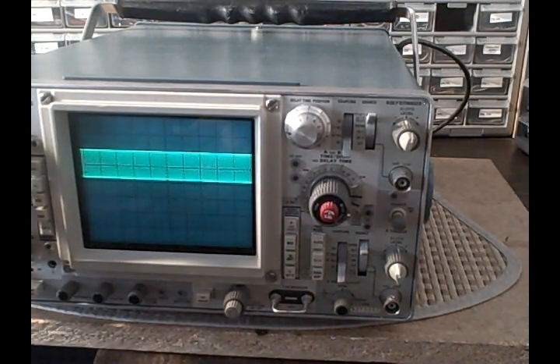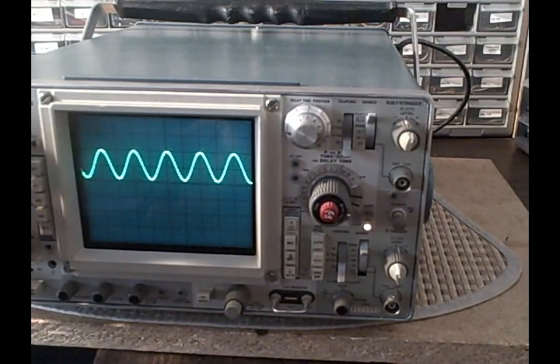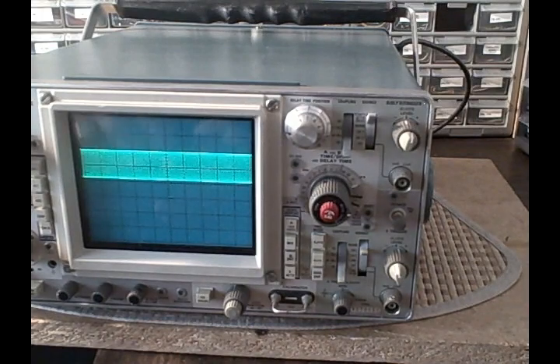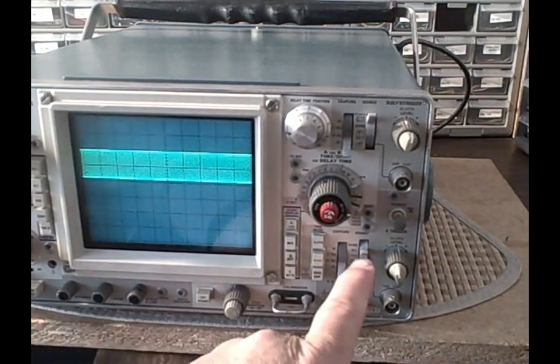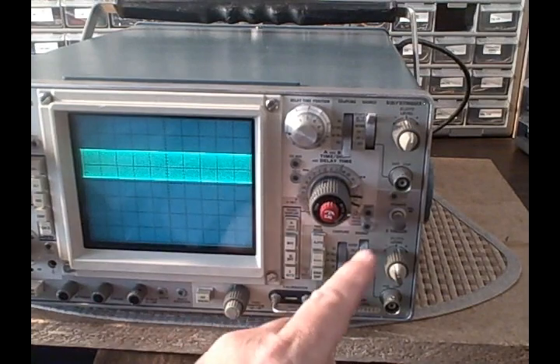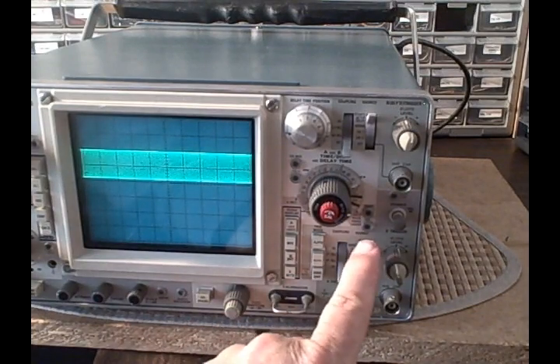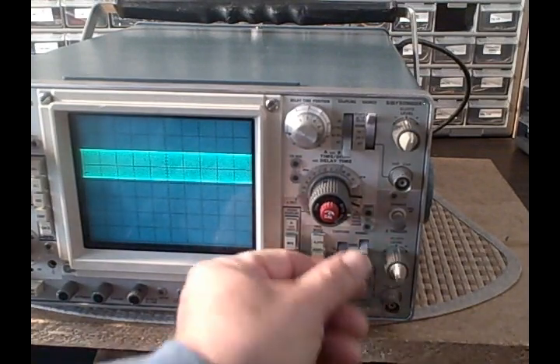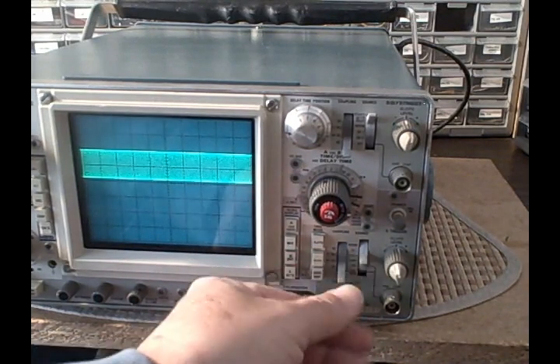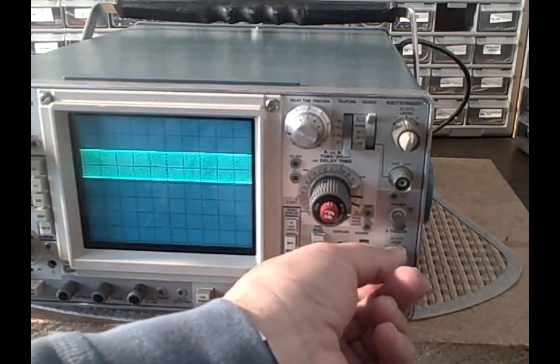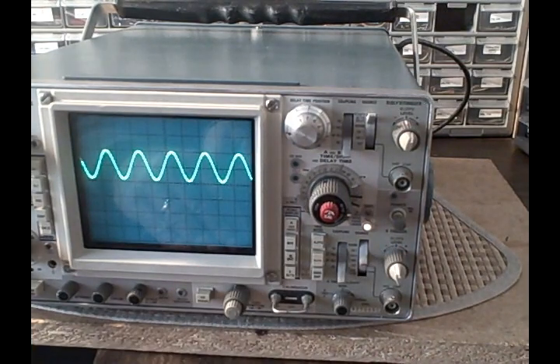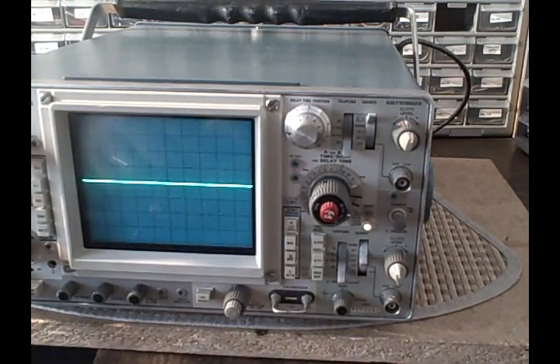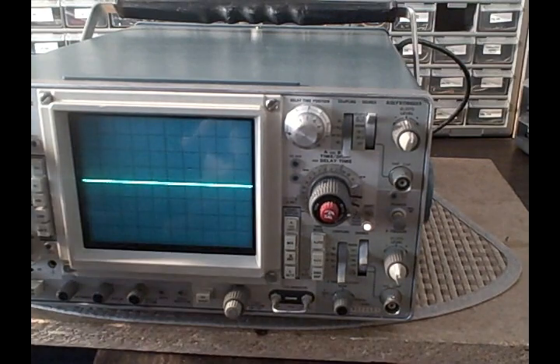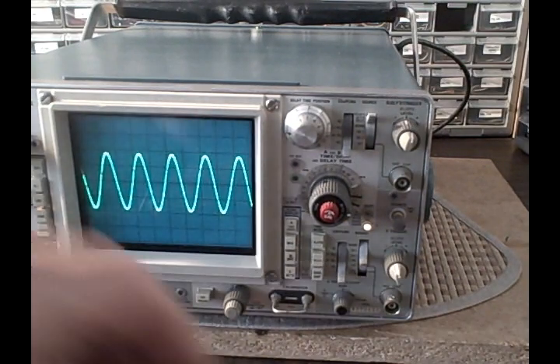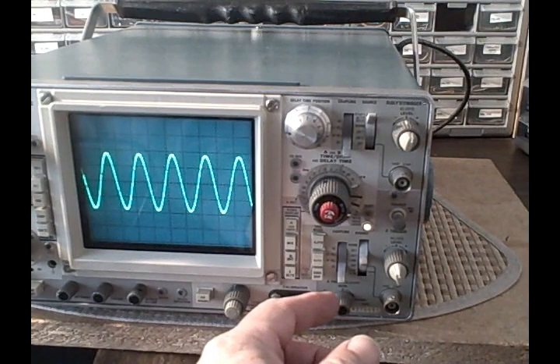And we can put one on 1 as well. Doing that. Well, if I don't have a channel 1 signal right now, because I'm triggering on channel 1, I don't have any lock. If I move myself with this switch here to channel 2 and adjust my lock, there it is. So I'm locked in on 2. If I go to 1, I have no display at the moment. Okay. That takes care of that.